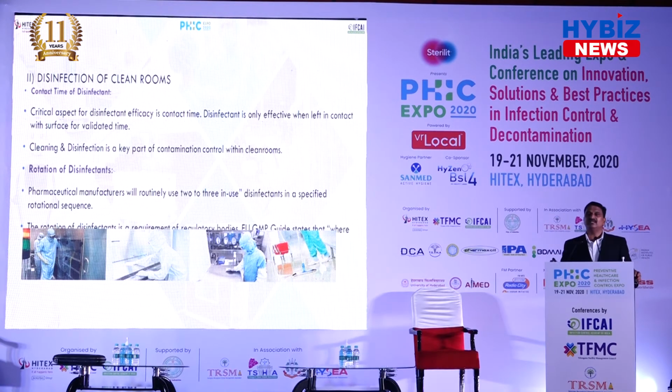Generally, the validated disinfectants should be rotated in a clean room, because if we keep on using a single disinfectant, there is a possibility of microbial resistance to the disinfectant. So these disinfectants should be rotated at least once in a week. Generally, around 2 to 3 disinfectants will be rotated in a pharmaceutical facility.